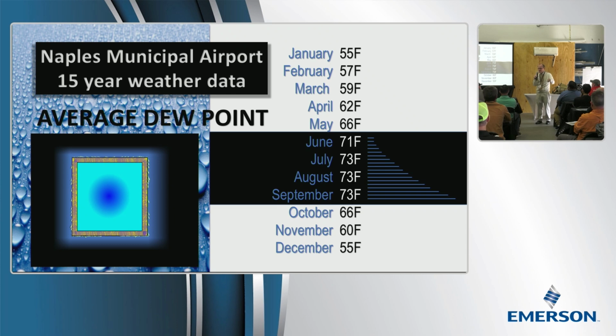That pink stuff. How many of you have a psychrometer that has 2 heads on it? Fieldpiece makes one. You like that? Isn't that nice? It's got 2 heads on it, so you always know if one's lying, right? Because they got to read the same thing. Next summer, when you're in one of these cases where the ducts are sweating and you see this pink, fluffy, blown-in insulation, Andy Oss turned me on to this. Stick one psychrometer tip down in the fluff, put the other one up in the air. It'll blow your mind how wet that insulation is.